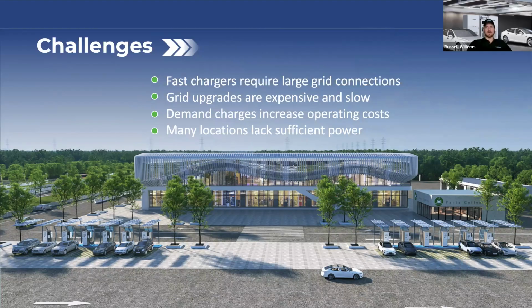The reason for that is that when you plug in a fast charger, it instantaneously draws a ton of power from the grid all at once. It says, give me as much as I can in inflow. When you have two or three of those running together, all of a sudden your site, which normally has a nominal draw from the grid supporting the lights and power, maybe 30 to 50 kilowatts at any instant, can shoot up to 80, 100 kilowatts with even as few as three EV chargers plugged in at once.